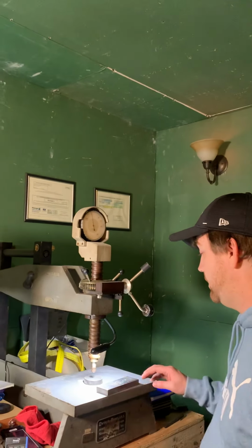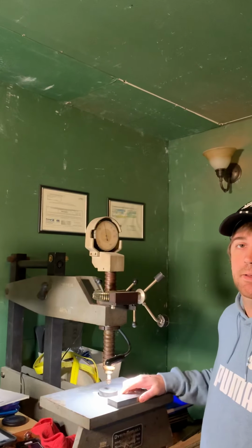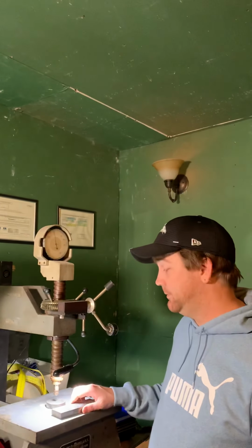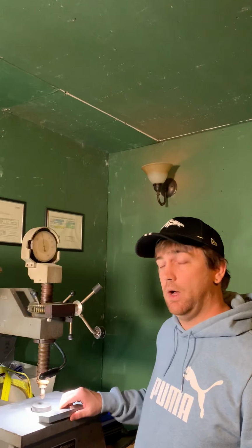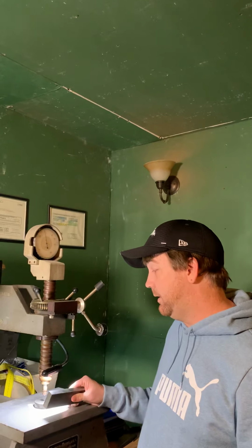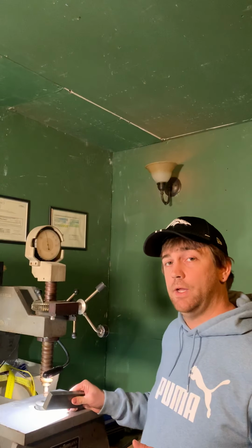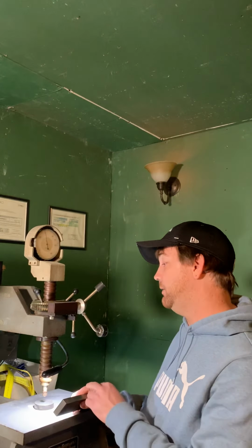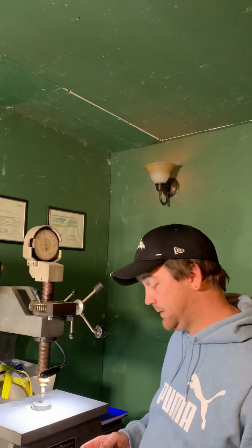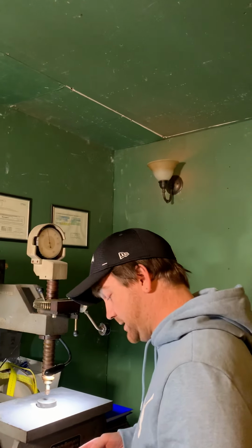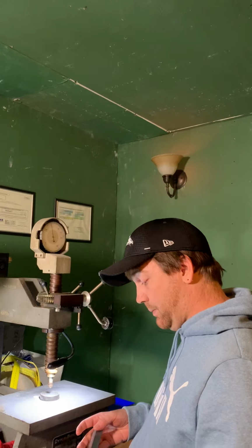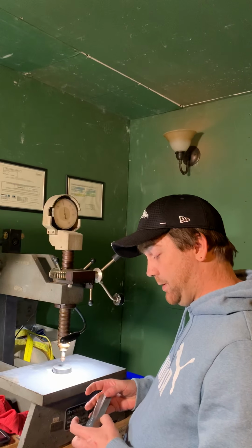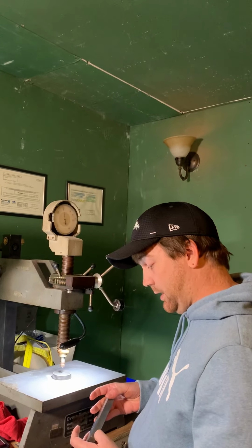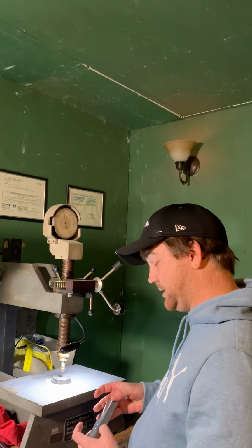This is how you do a Brinell indirect verification under ASTM E10-18. The first thing that you do is get 2 blocks for the low and the high range for the force and the millimeter of the ball that you're going to be testing. This one is a 10 millimeter diameter ball, and it is a 3,000 kilogram load.